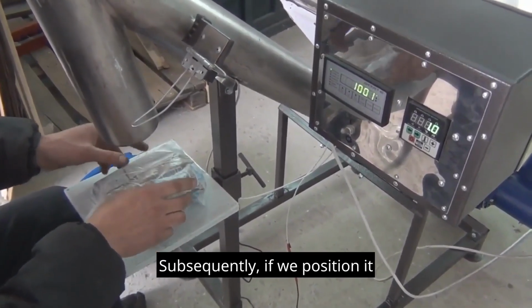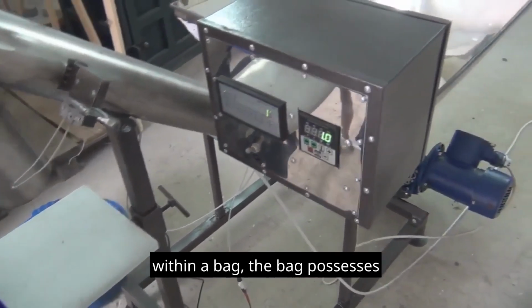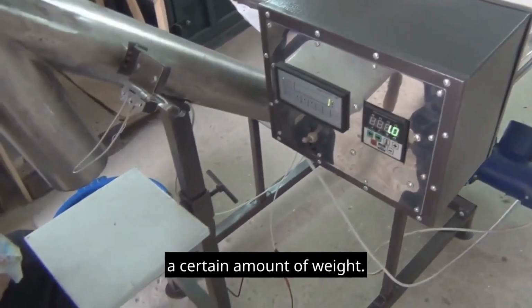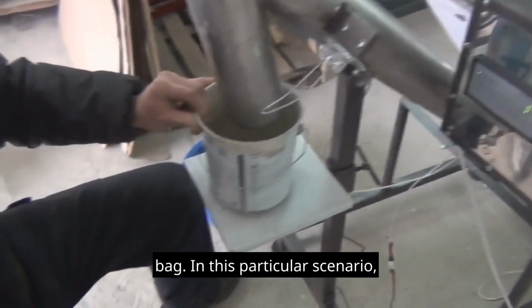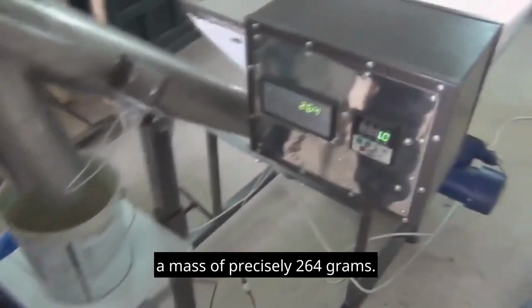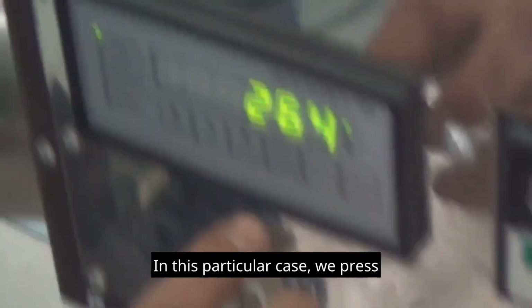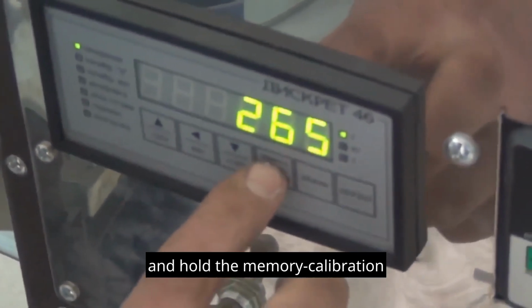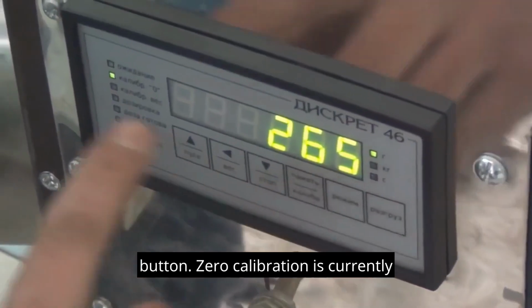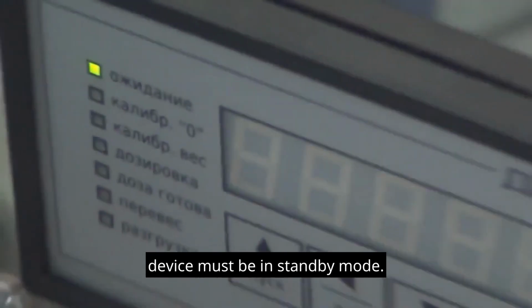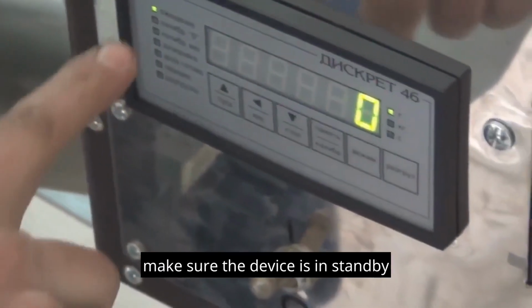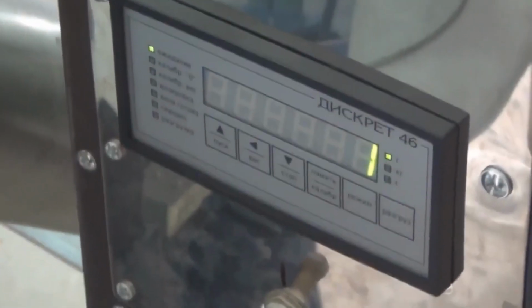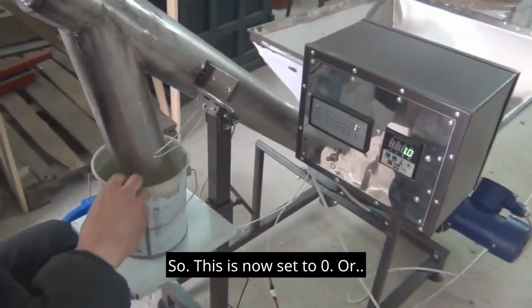Subsequently, if we position it within a bag, the bag has a certain amount of weight. We will proceed to insert the bag. In this scenario, we have this container. It has a mass of precisely 264 grams. In this case, we press and hold the memory calibration button and then press the mode button. 0 calibration is in progress. Prior to this, the device must be in standby mode. Therefore, we either power it off and back on, or we press the stop and unload buttons to make sure the device is in standby mode. So, this is now set to 0.